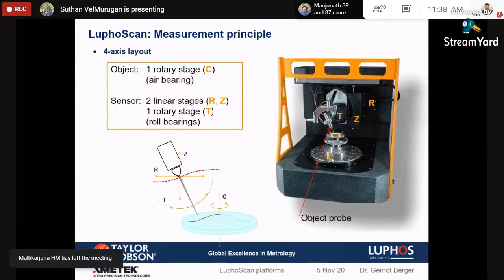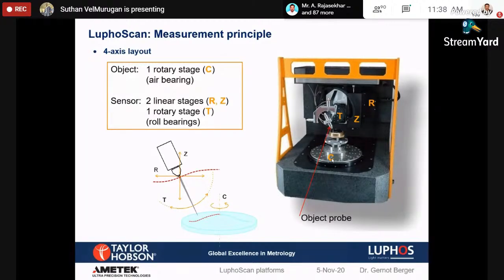For example, if we are going to measure a sample that is a rough cut and not a finished sample, my error will be in the order of 200 to 300 nanometers. We can rotate at high speed, up to 100 RPM or 90 RPM, and measure it. If you are looking for something like 25 to 30 nanometer form error, we need to reduce the speed to around 25 to 30 RPM. That can be defined, and that is the important part. We can define it before we start the measurement.